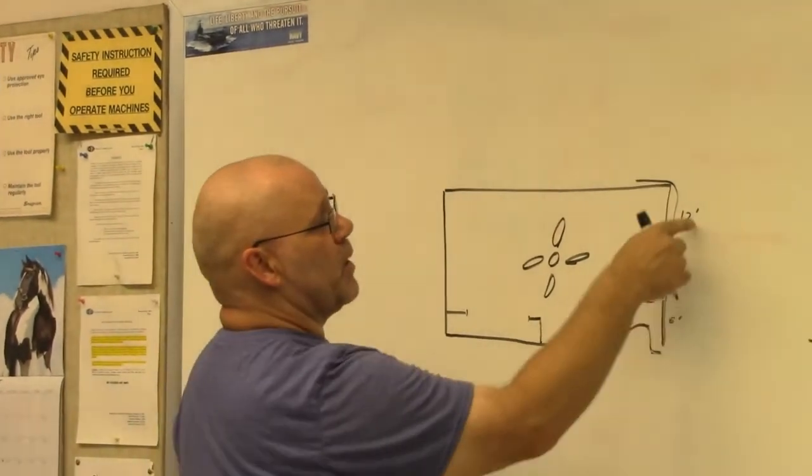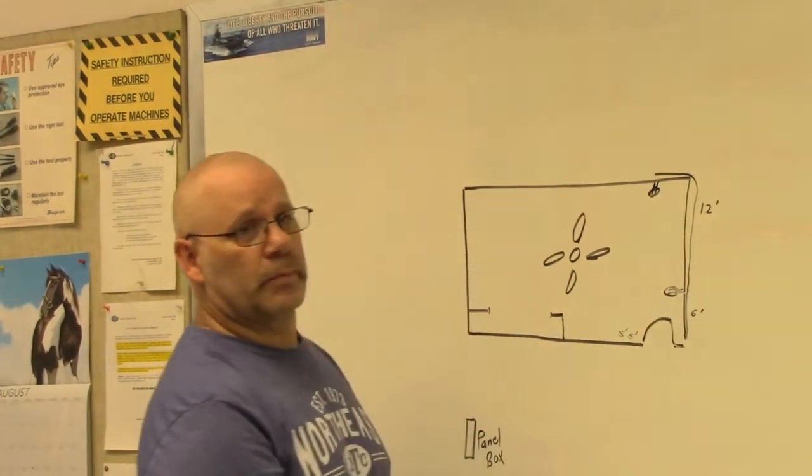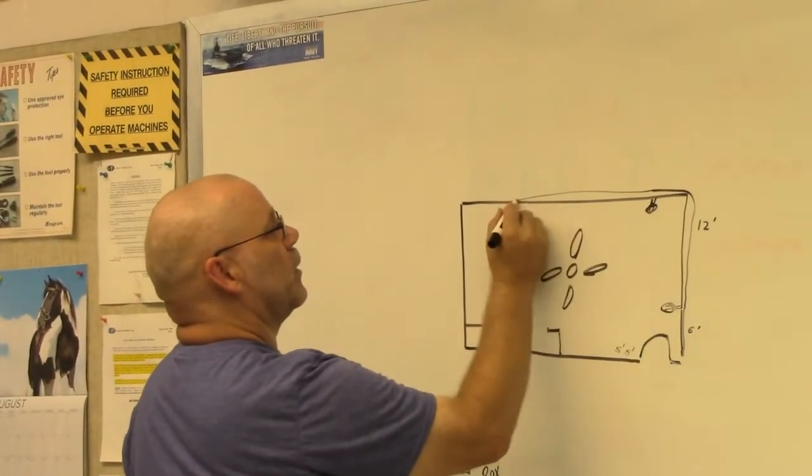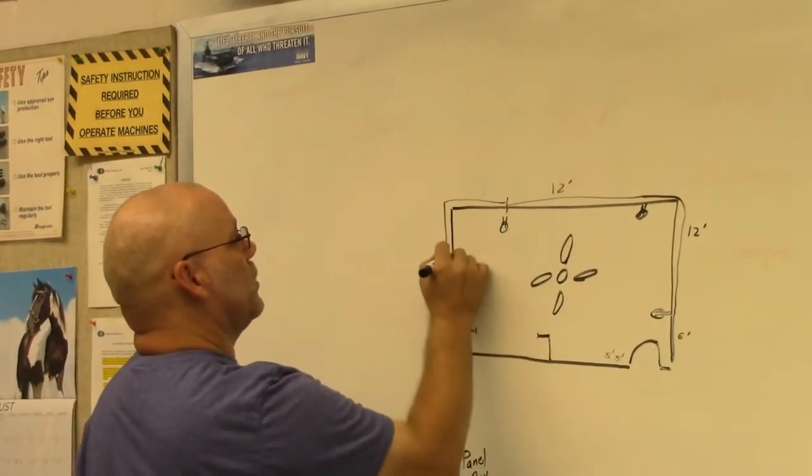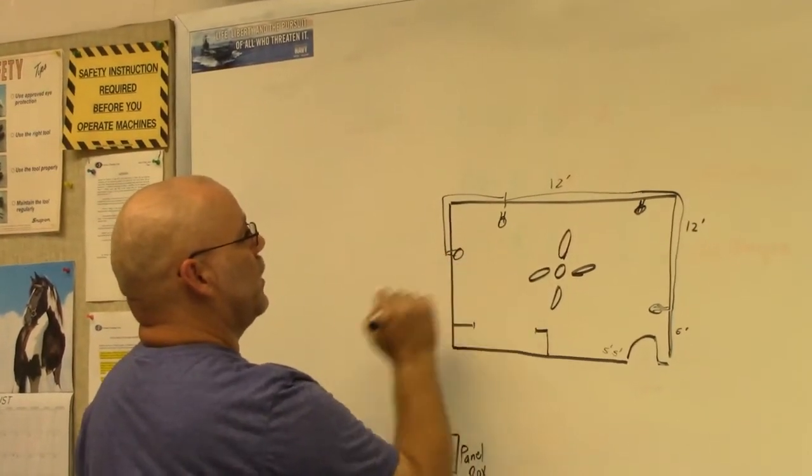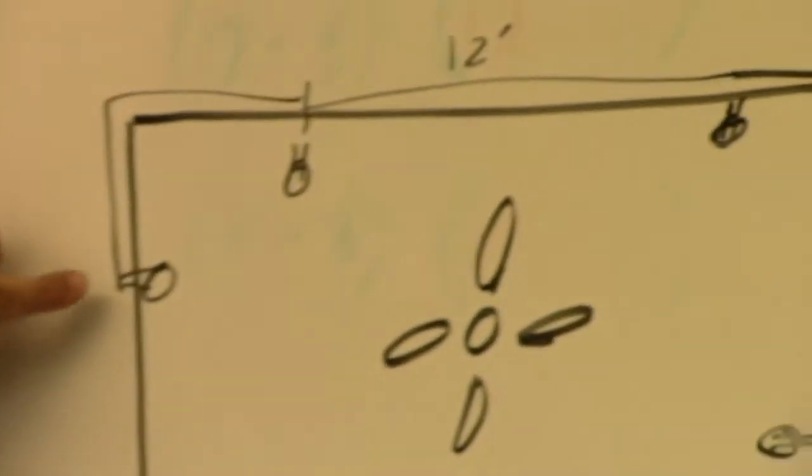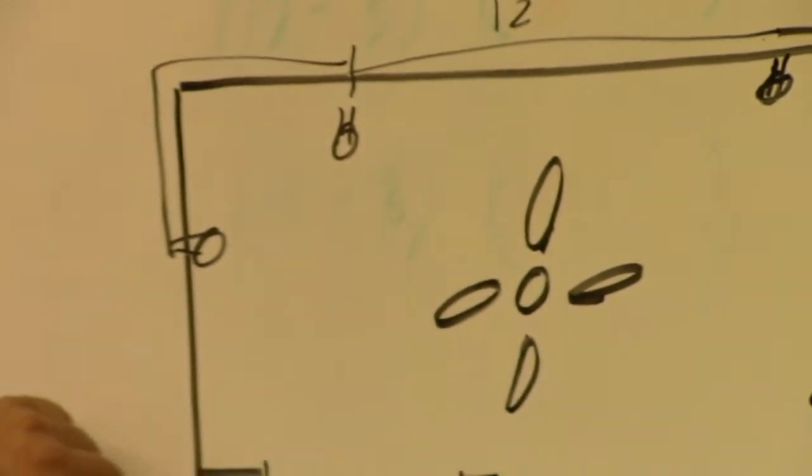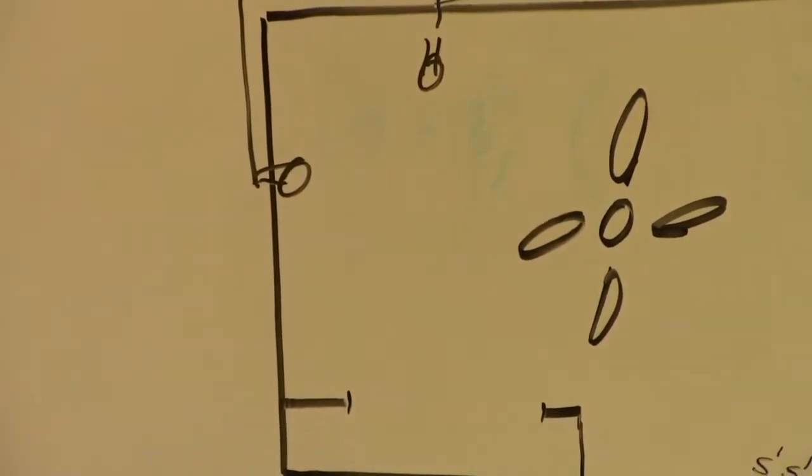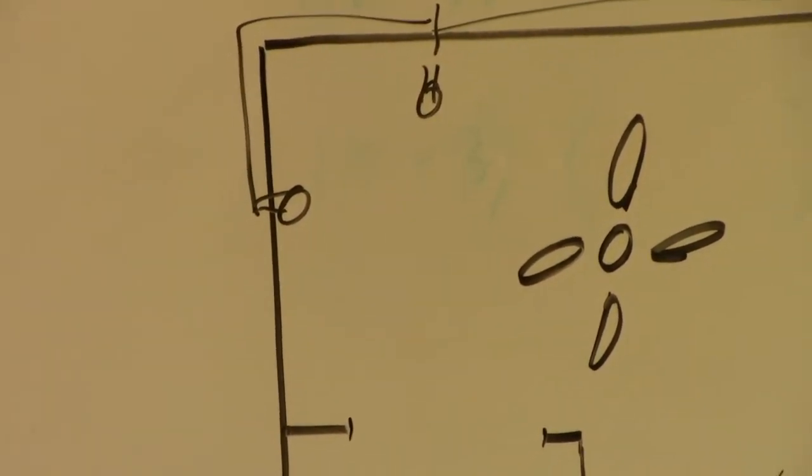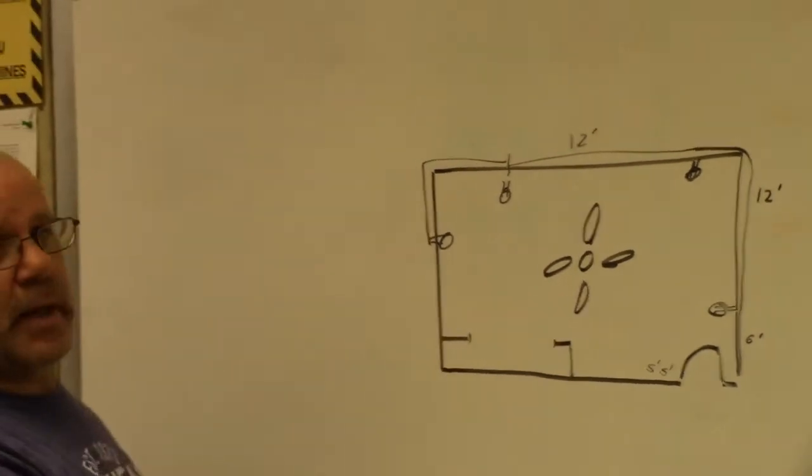So I'm going to measure up to 12 feet and put the outlet symbol. Measure 12 more feet, outlet symbol, 12 feet, outlet symbol. Now if this distance is more than six feet, I have to add another outlet. If it's six feet or under, I'm good. So I'm going to say that this is less than six feet.